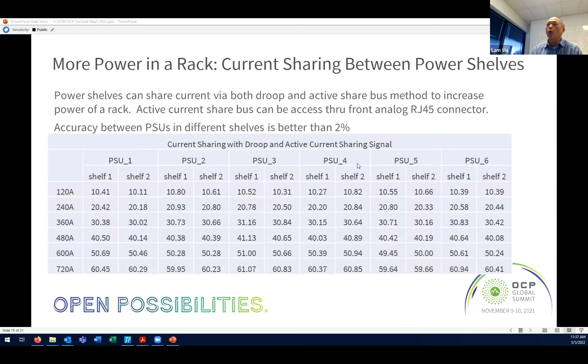When you talk about what happens if we want to parallel power shelves, we ran some tests, and we can show that with the daisy chain current-sharing connector, the power supplies between power shelves can have current sharing of less than 2%. In case the connector isn't connected, or gets disconnected, the power shelves with the droop feature can still share current, but in this case the current sharing is worse—less than 10%, but still within a workable boundary.